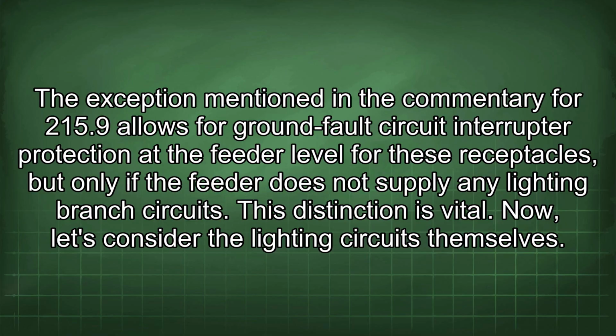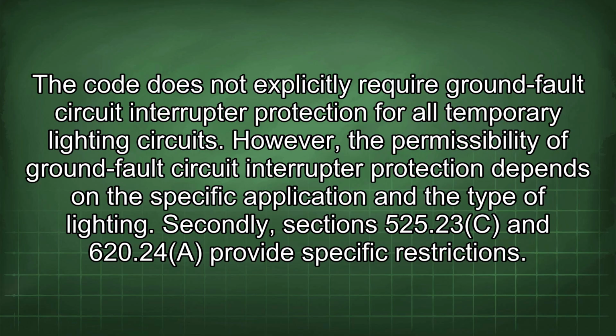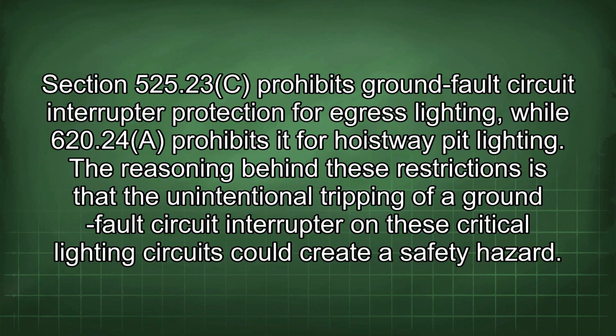This distinction is vital. Now let's consider the lighting circuits themselves. The code does not explicitly require ground fault circuit interrupter protection for all temporary lighting circuits. However, the permissibility of ground fault circuit interrupter protection depends on the specific application and the type of lighting. Secondly, sections 525.23(C) and 620.24 provide specific restrictions. Section 525.23(C) prohibits ground fault circuit interrupter protection for egress lighting, while 620.24 prohibits it for hoistway pit lighting.